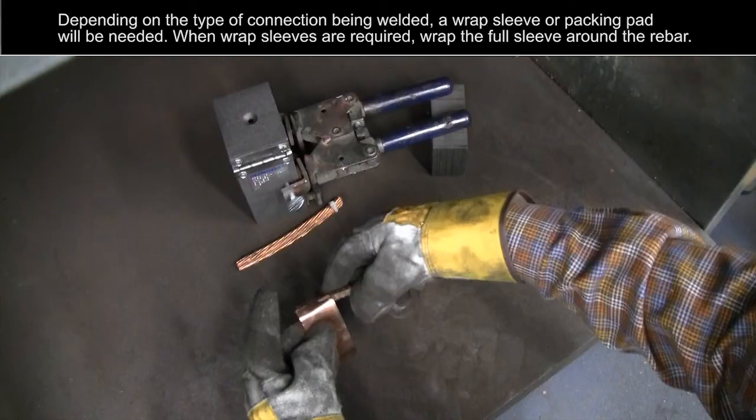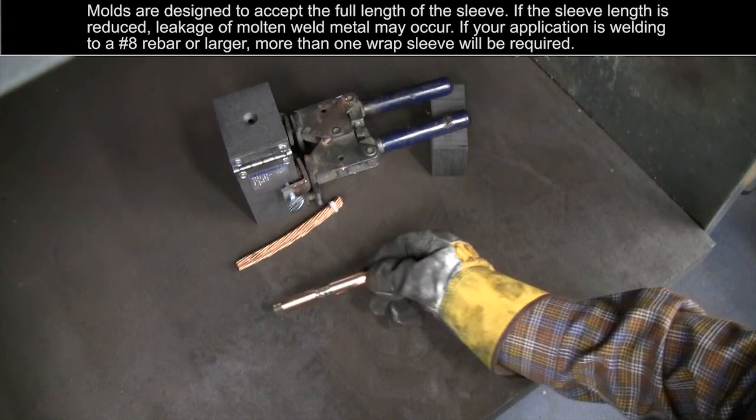Depending on the type of connection being welded, a wrap sleeve or packing pad will be needed. When wrap sleeves are required, wrap the full sleeve around the rebar. Molds are designed to accept the full length of the sleeve. If the sleeve length is reduced, leakage of molten weld metal may occur.